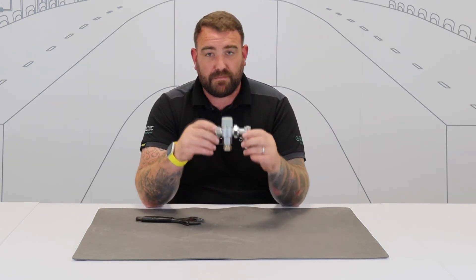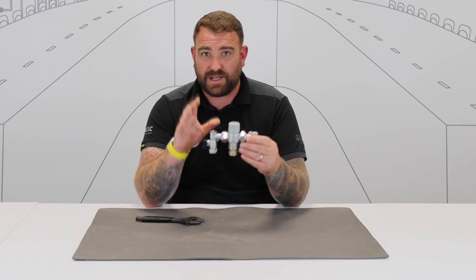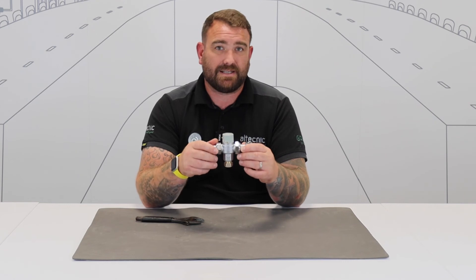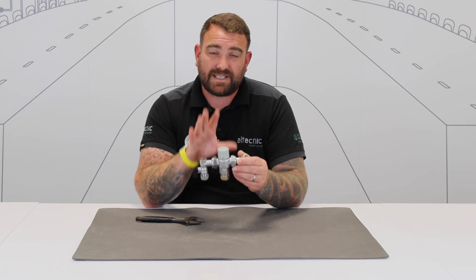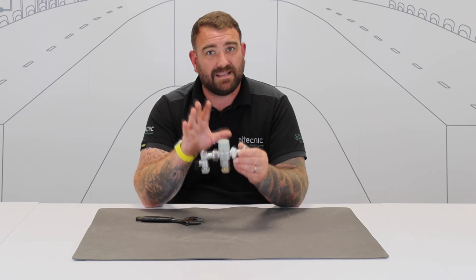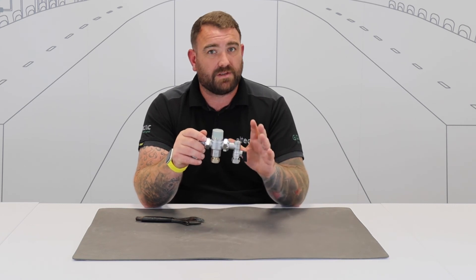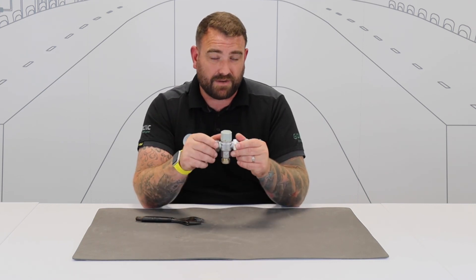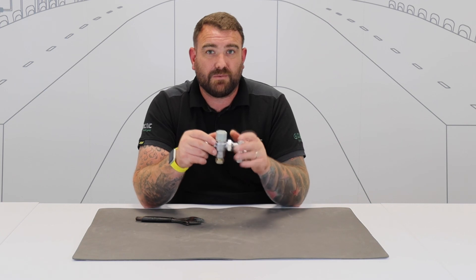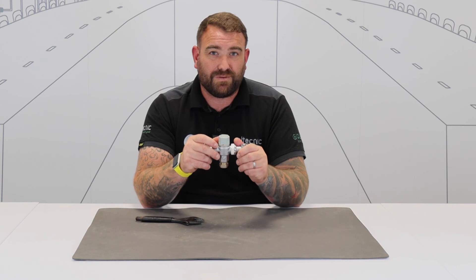Now what we need to do is run the temperature of the valve and make sure we've got back to the set point where we were before. And that's all that really is when it comes to the cleaning and maintenance of this thermostatic mixer valve. It's not too difficult, but it's really important to make sure the valve is still delivering a safe set temperature, and that should the cold water be isolated, the valve will shut off and not deliver raw hot water with a scalding risk. If you want any more information on this valve — IOMs, data sheets, or any other products in our Altecnic range — please visit our website at www.altecnic.co.uk. Thank you for watching.